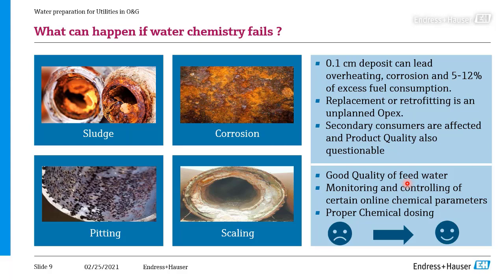Steam, if you deal with it in a high pressure, high temperature environment, what can happen is corrosion. If you do not maintain oxygen on a very low level, that causes corrosion - same for pH. You have build up here, scaling - for example, scaling from silica, from hardness, from sodium. That blocks the pipe at the end of the day, and also lowers the heat efficiency of the heat exchangers.